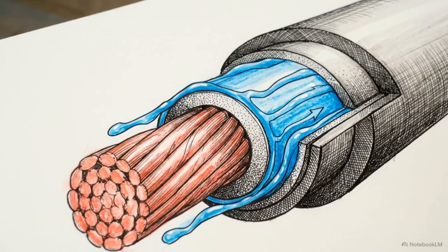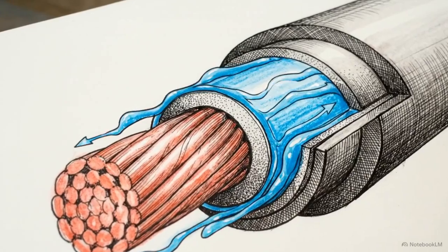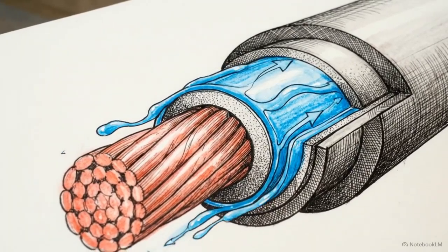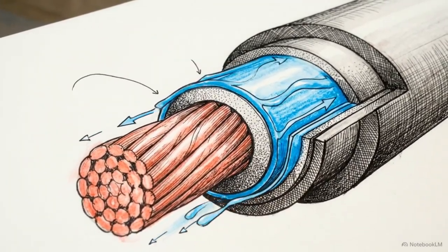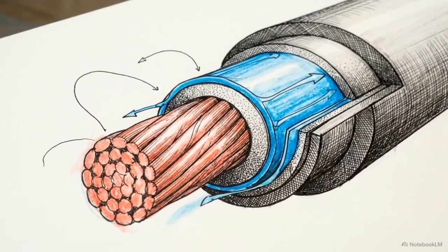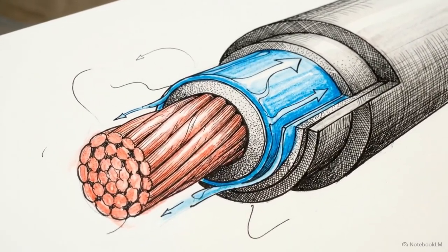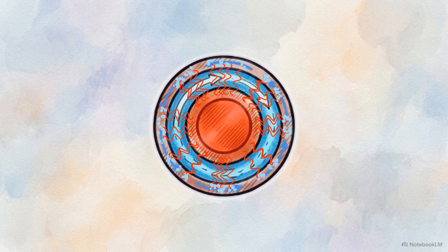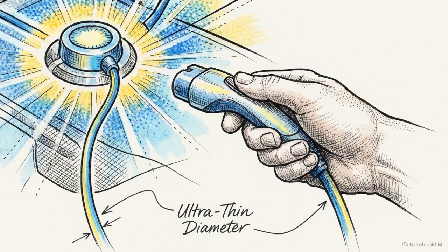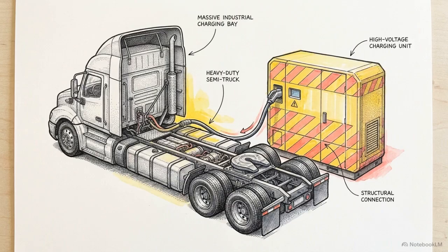Even with highly efficient chips, mechanical thermal management is still required. Fast chargers rely on active liquid cooling loops running continuously inside the charging cables themselves. This circulating fluid strips heat directly off the internal copper wires, allowing the cable to remain thin and light enough for a person to handle comfortably, while safely carrying massive electrical currents. We will need every bit of that cooling capacity.